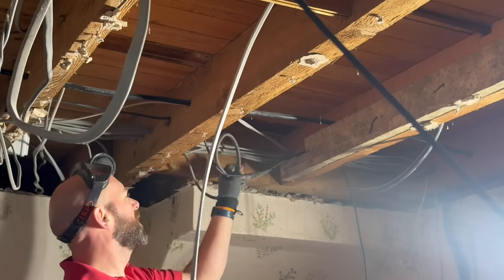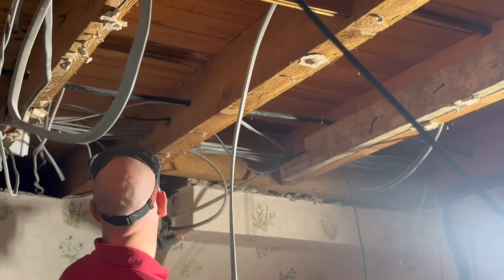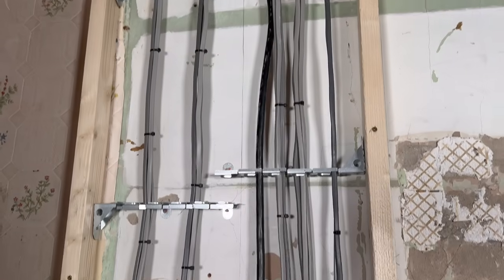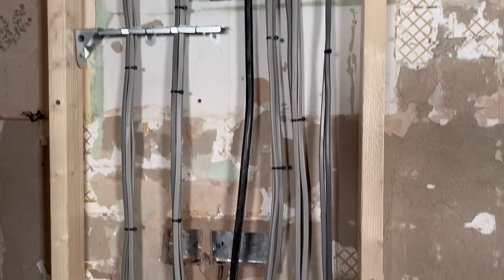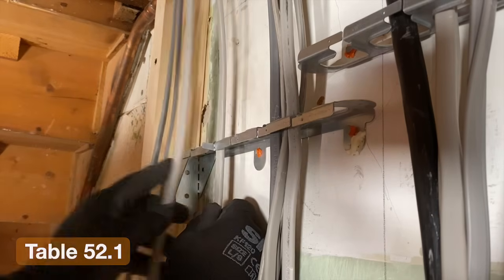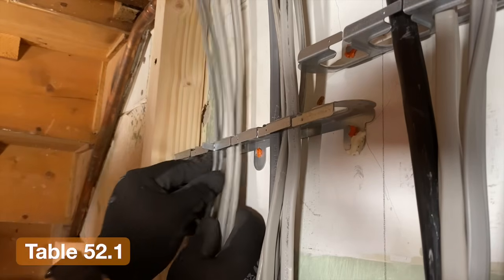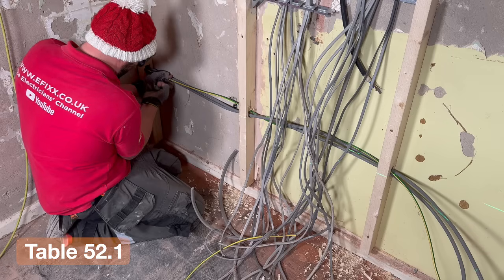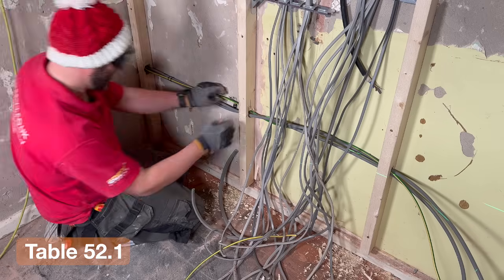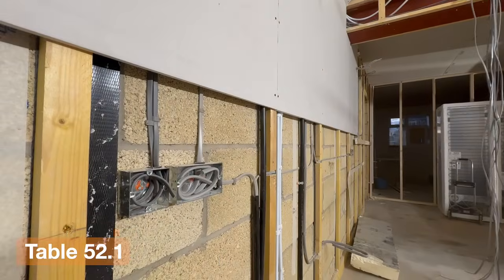But keeping cables together is only one part of the story, because once those cables leave the enclosure and start running through walls or partitions, the risks change. And this is where Amendment 4 introduces something new. We have a new table, Table 52.1. This sets out the requirements for cables concealed in walls or partitions. What this does is bring much clearer guidance based on two key things: the construction of the wall and the depth of the cable from the surface. So instead of relying on interpretation, you now have defined requirements to follow.